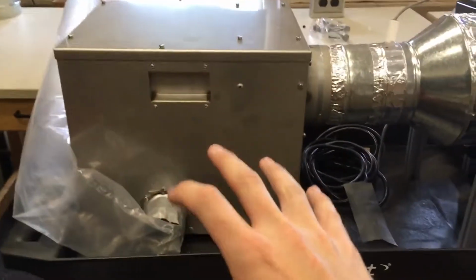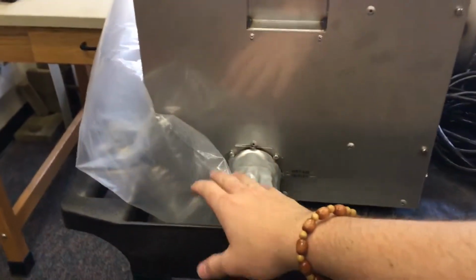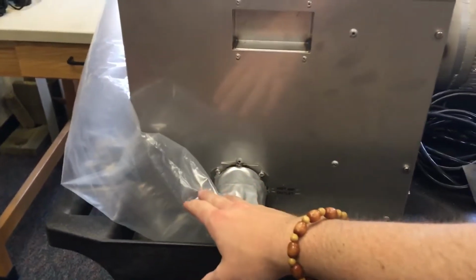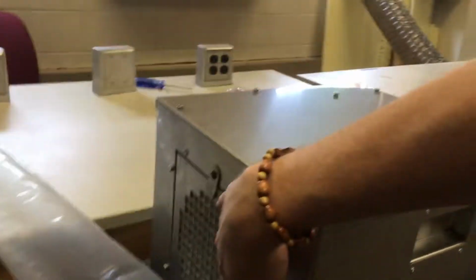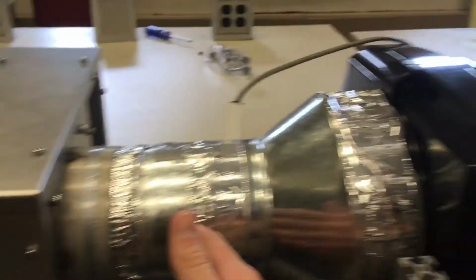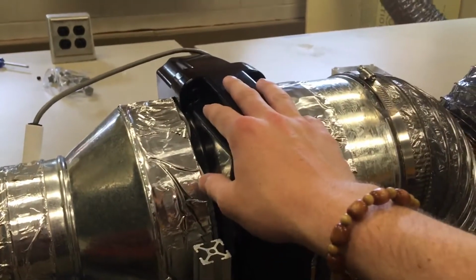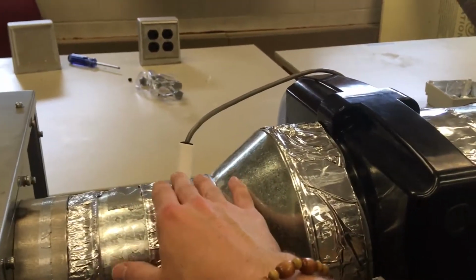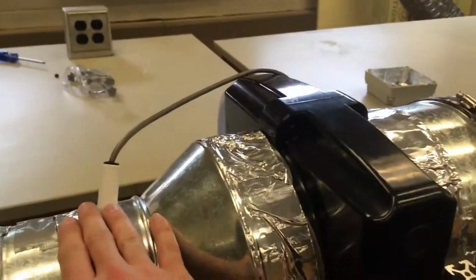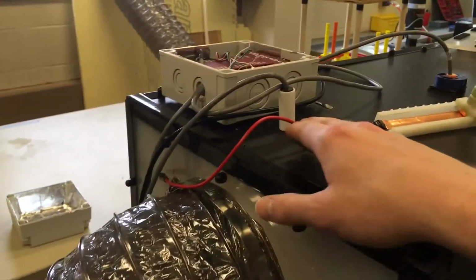A little demonstration of what's going on. This is the wet, hot air coming out of the desiccant dehumidifier, and that's being fed outside. And then this is the inlet. This is the outlet, and it goes into a chiller coil. And then there is a temperature and humidity sensor before that coil, and then one after.